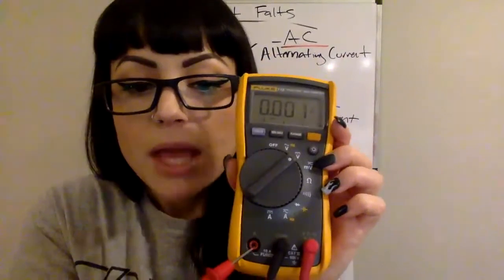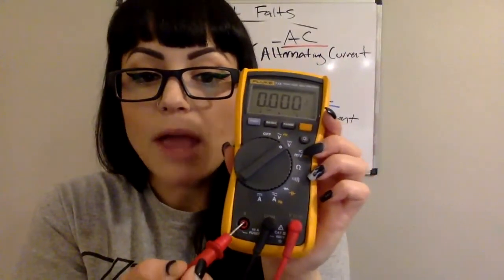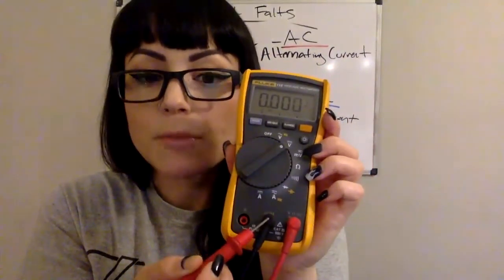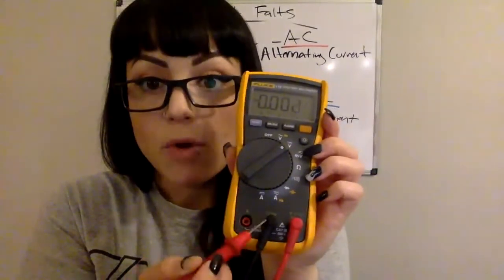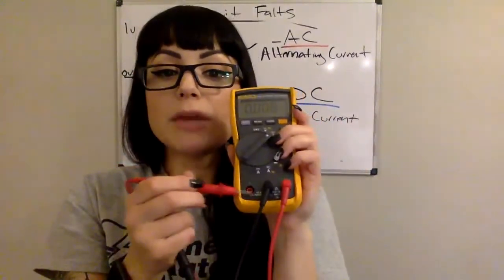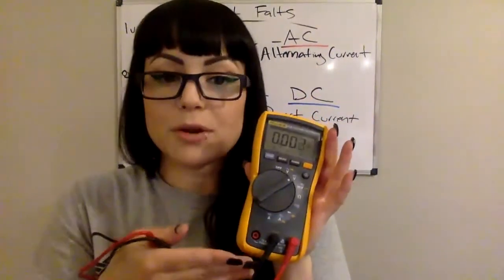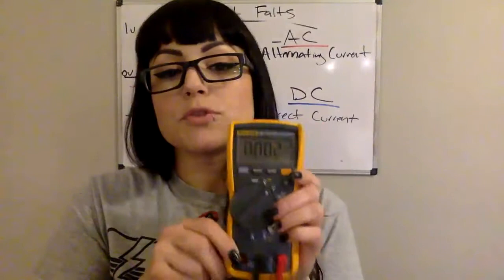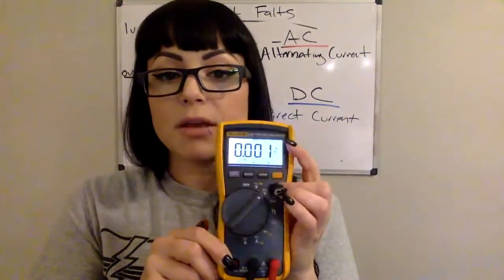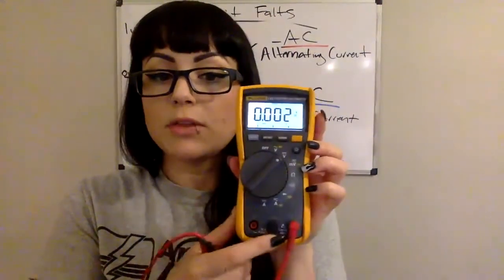Here's the problem. Between the A or amps hole and the COM terminal, I have zero. So if I have my meter hooked up into the amps terminal and the COM terminal, and I hook this across a battery, I simply created a short circuit, and you will let the magic smoke out of our Fluke meter here, or your meter at home. So don't do that. You definitely want to make sure you're in the correct hole.